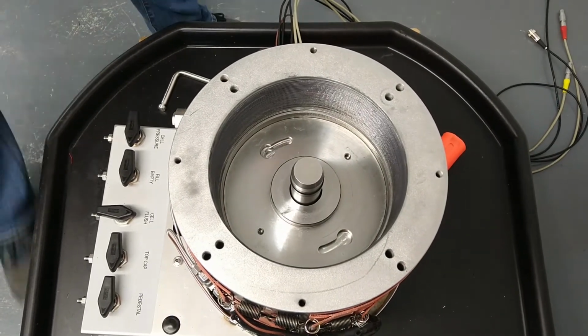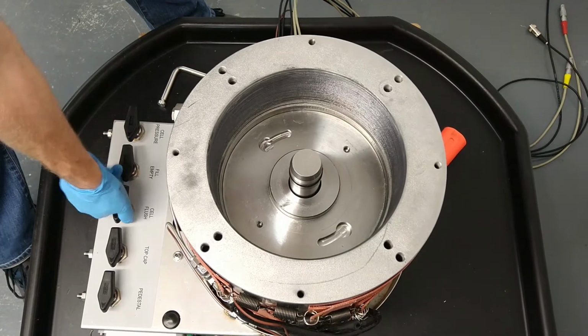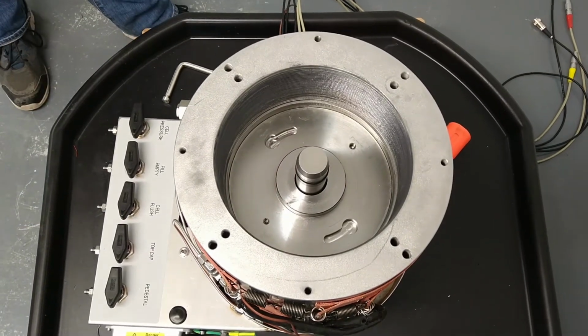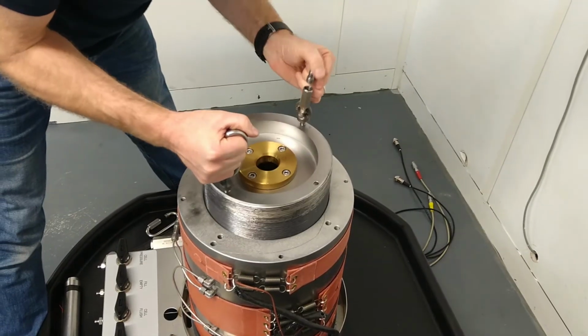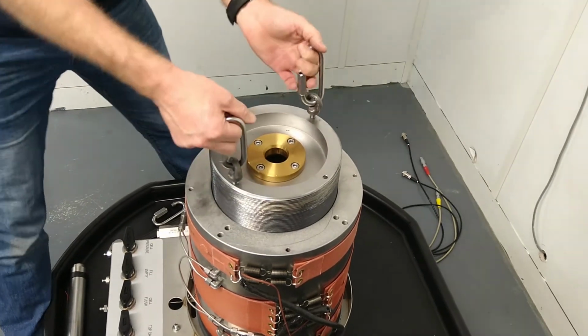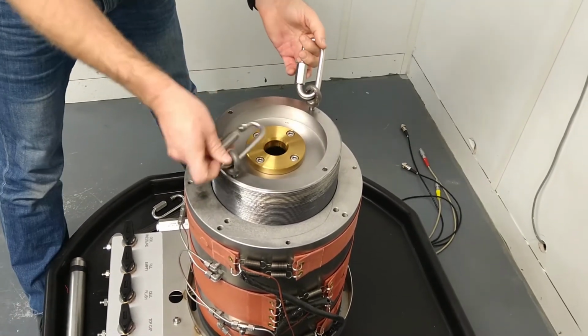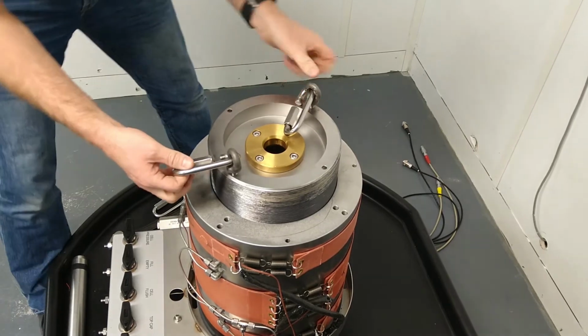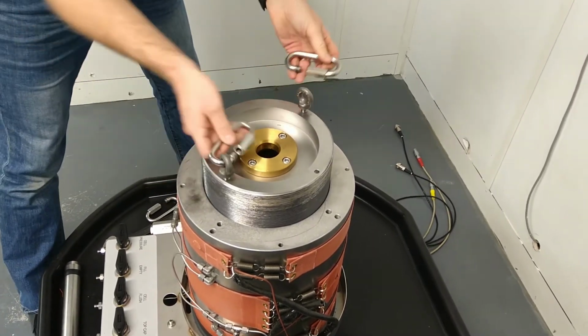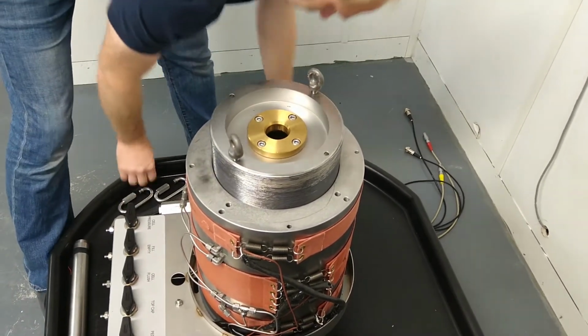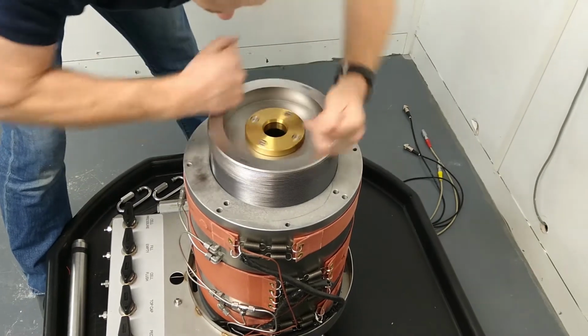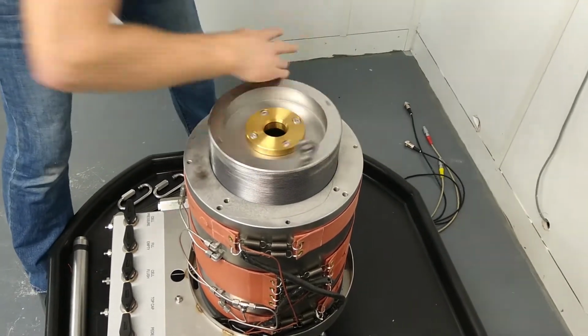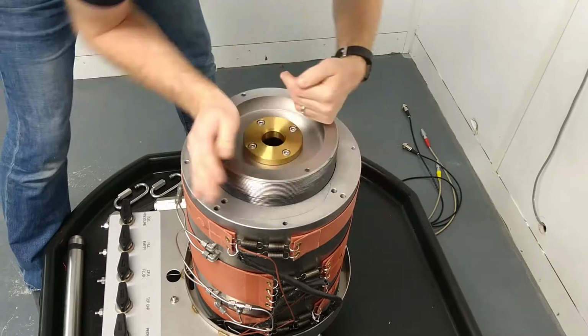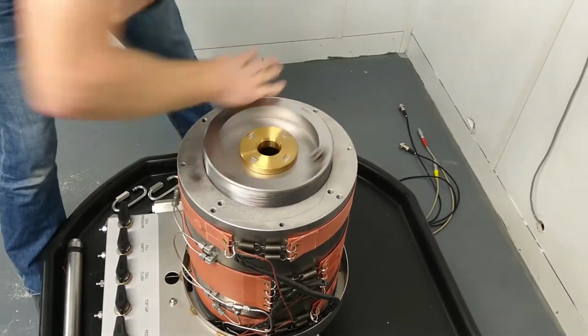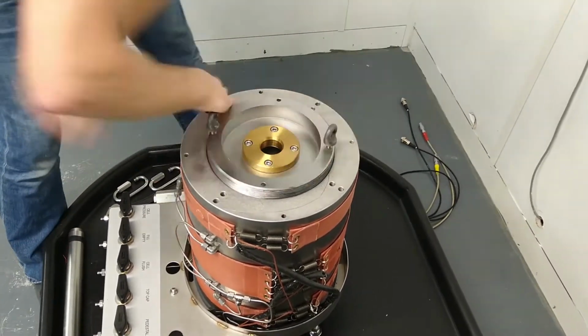Fit the lifting points onto the cell top for safe lifting and the placement of the cell top. Gently lower the cell top onto the cell wall. If required, use 2 persons. Slowly rotate the cell top until the thread engages correctly. Do not force the top to rotate if it is not moving freely. Unwind and re-engage the threads. Continue to wind the cell top until flush with the upper edge of the cell wall.